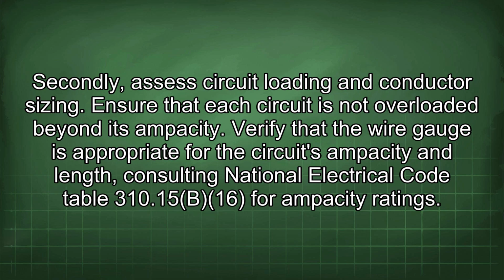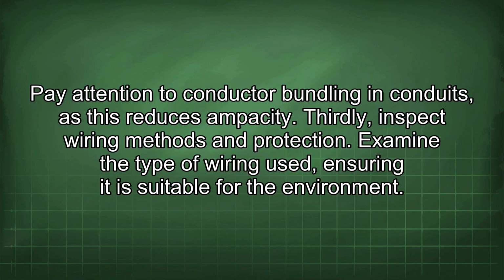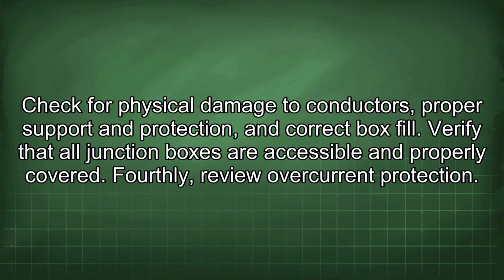Secondly, assess circuit loading and conductor sizing. Ensure that each circuit is not overloaded beyond its ampacity. Verify that the wire gauge is appropriate for the circuit's ampacity and length, consulting National Electrical Code Table 310.15(B)(16) for ampacity ratings. Pay attention to conductor bundling in conduits, as this reduces ampacity. Thirdly, inspect wiring methods and protection. Examine the type of wiring used, ensuring it is suitable for the environment. Check for physical damage to conductors, proper support and protection, and correct box fill. Verify that all junction boxes are accessible and properly covered.